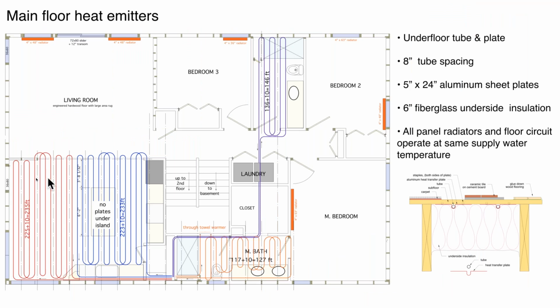This is a tube and plate underfloor system for a kitchen and dining room area. That layout takes a little bit more time. This is where the tubing is 8 inches on center, aluminum plates. Same thing in the bathroom here, okay? And then you'll see these orange rectangles. These are the panel rads. 2 of them in here, one in that bedroom, one there, and then the larger one in the master bedroom, okay? So again, it's a combination.